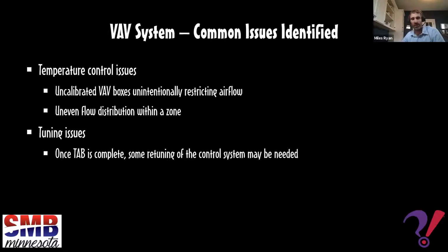One of the makeup air units serving one of the towers had been operating probably since the May timeframe. And the controls contractor, a very good contractor, spent a lot of time working with control sequences, because they were pretty sophisticated. There was no glycol in this particular system, for reasons I won't get into, and that resulted in very complicated control sequences to protect those coils against freezing during all different situations. He spent a lot of time tuning all of the control loops and making sure that everything worked seamlessly during every possible scenario it could encounter.